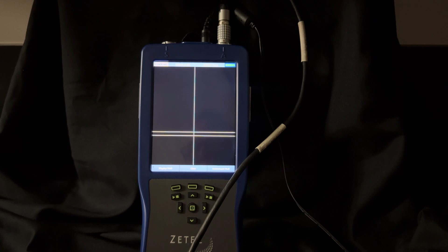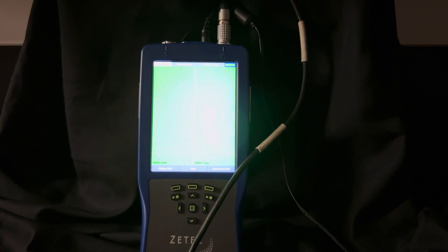The reason the screen is black is because my encoder wheel is not moving, indicating the probe is not moving. But as soon as I'm wiggling my probe it's going to start to display data, so I'm just going to move my probe back to the beginning of the row of rivets.